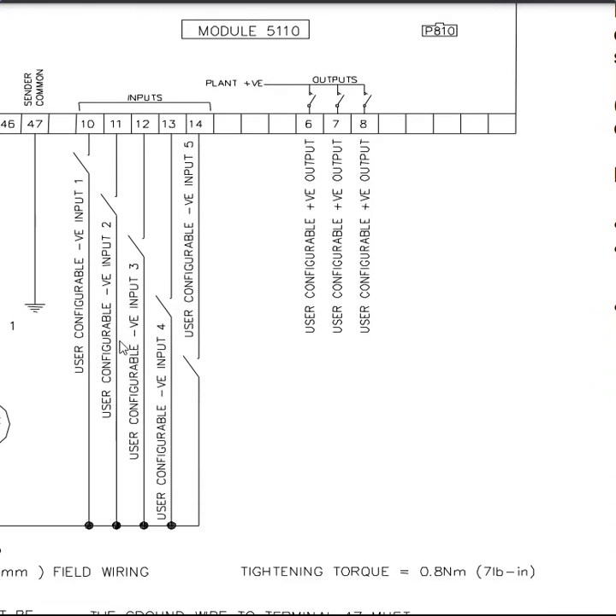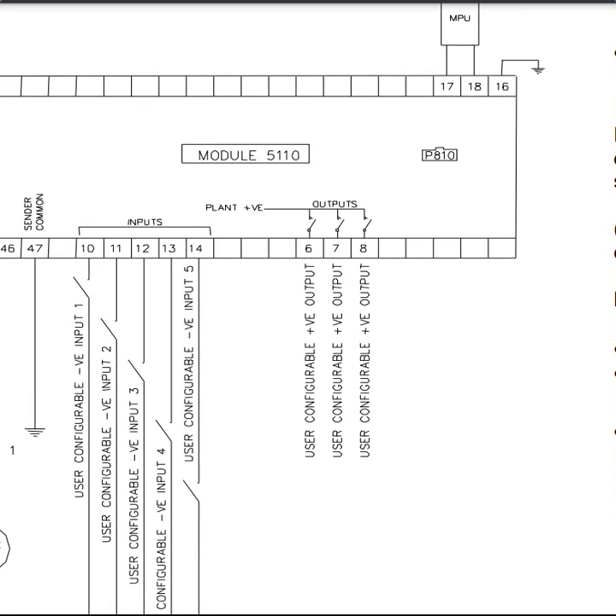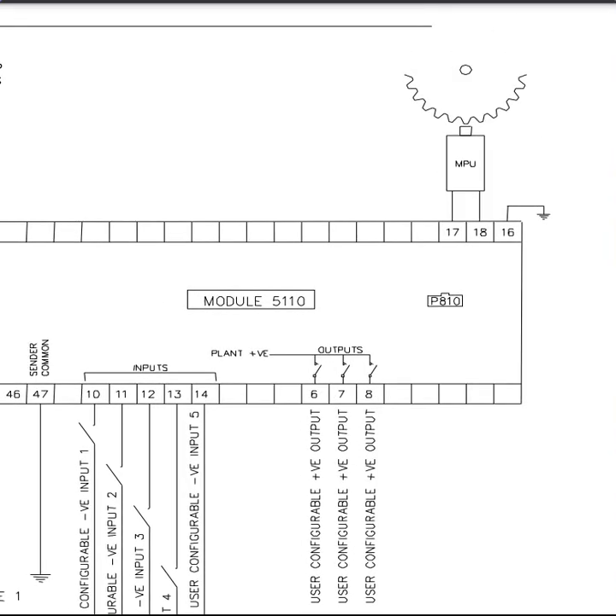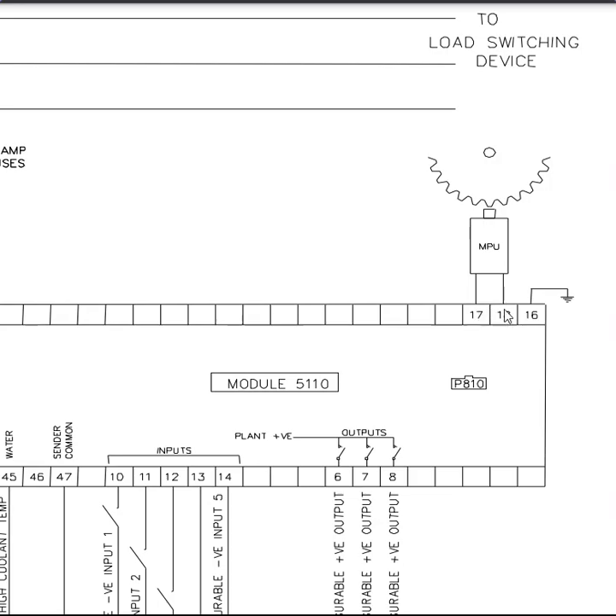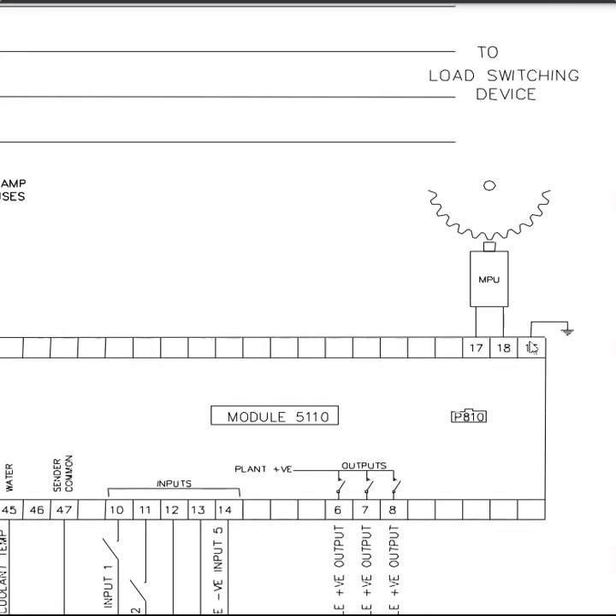So, user configurable input is going to be digital. Mag pickup, 17 and 18, and then you're more than likely going to have the shielded ground, 17, 18, and 16. The mag pickup is going to have a shielded cable most of the time. You're going to take the two regular wires and put them here, and then you'll have that ground that most of the time is not insulated. It's literally just a plain ground wire. Usually it's aluminum too, not copper. And you're going to put that right here.